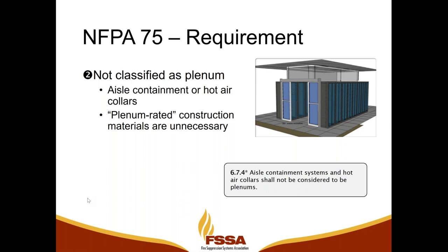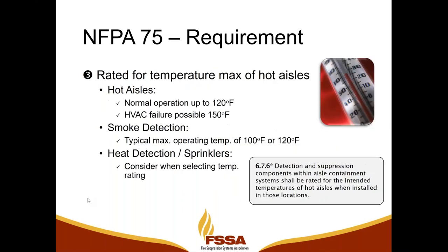But they do refer to point one, where the aisle containment materials, again, need to meet certain flame and smoke spread rating requirements. Point number three in NFPA 75 is that equipment needs to be rated for the temperature maximum of hot aisles.